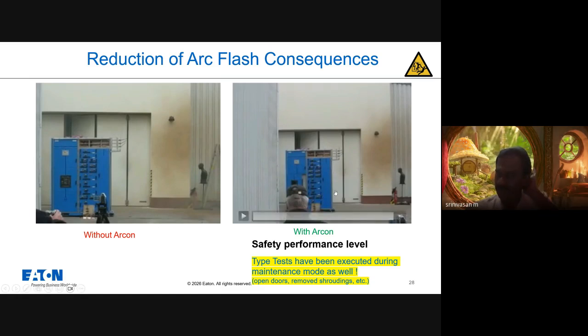Normally, when manufacturers or panel builders go for type testing, especially for internal arc, they pay very high attention to ensure that the doors are secured, closed and locked properly. But by having this Arcon, or quenching device, they keep the door open with confidence. That means safety to the human being, and also safety to the switchboard. So that is the level of safety offered by the Arcon.